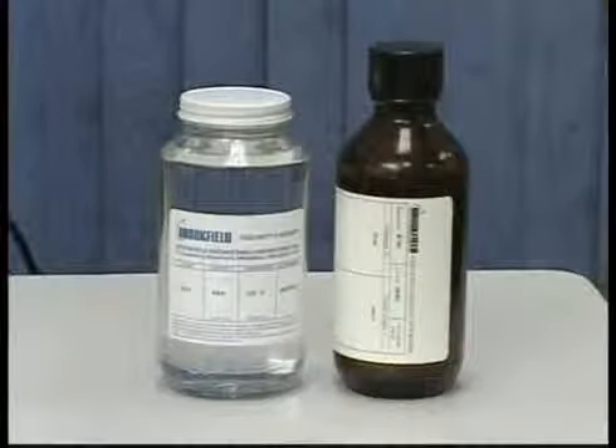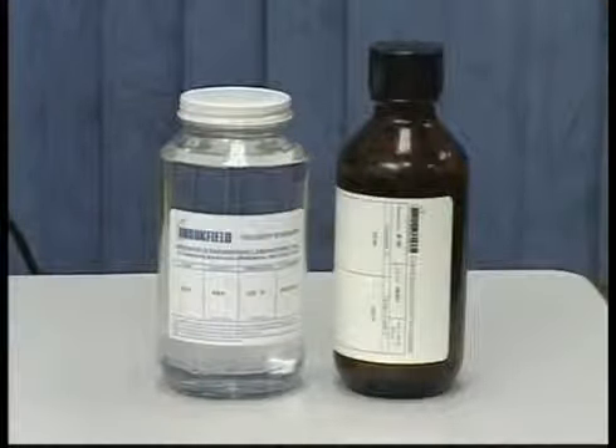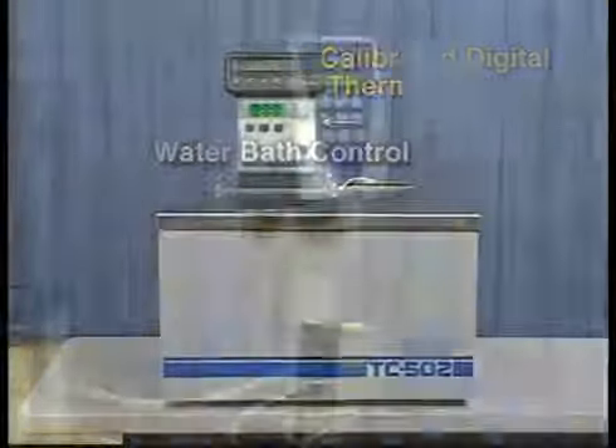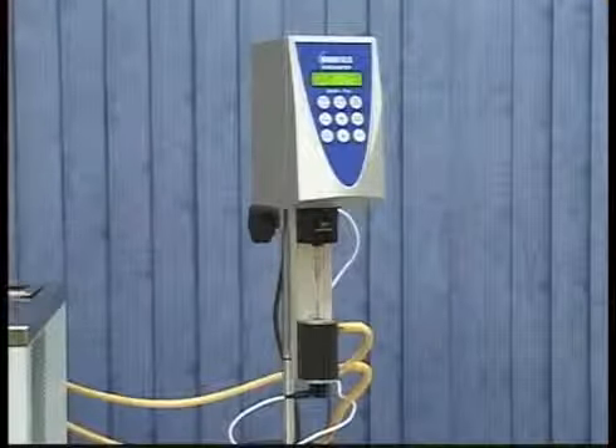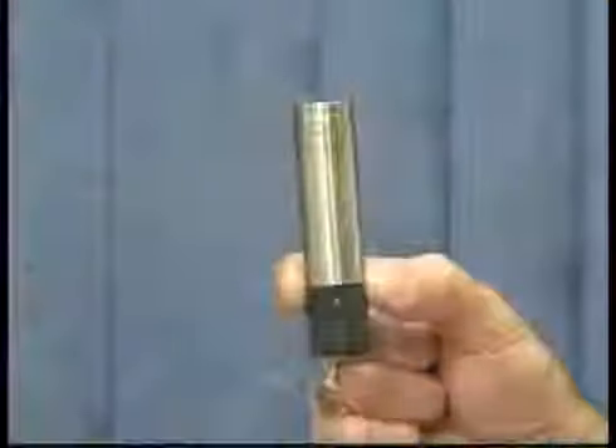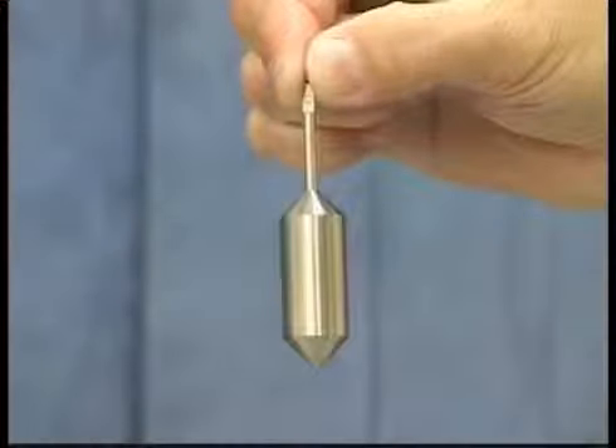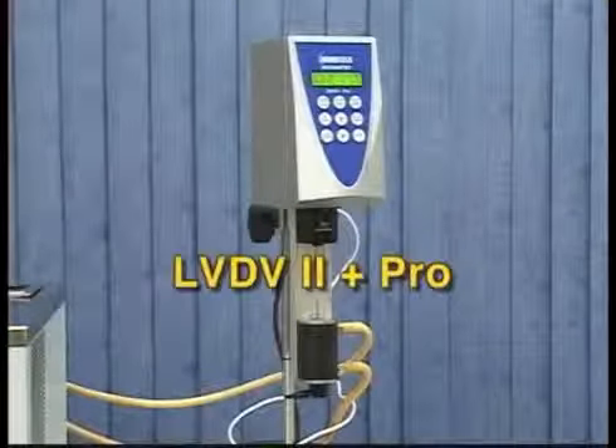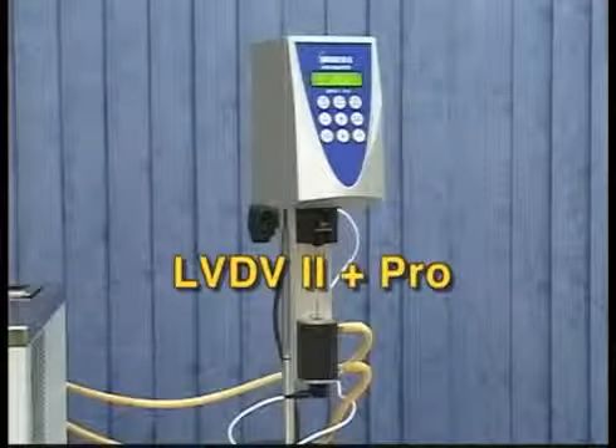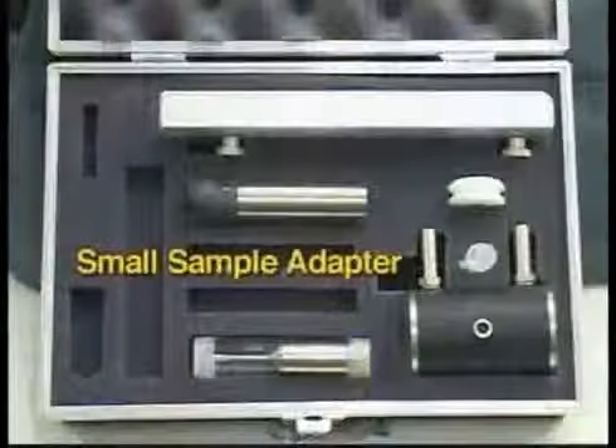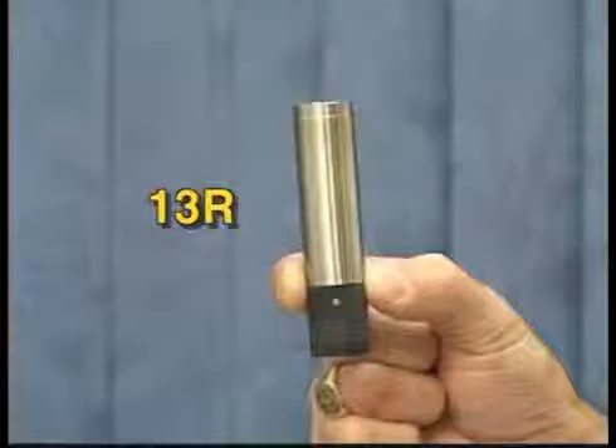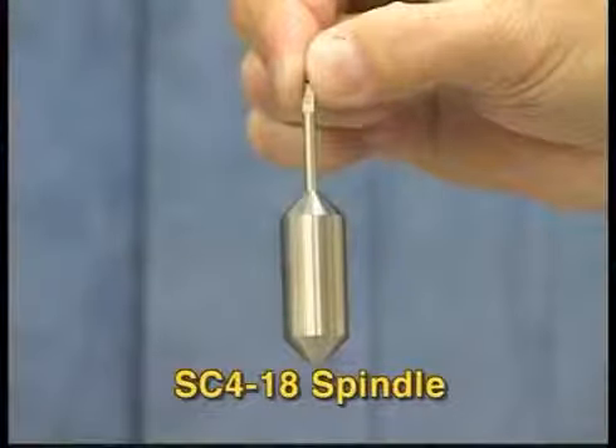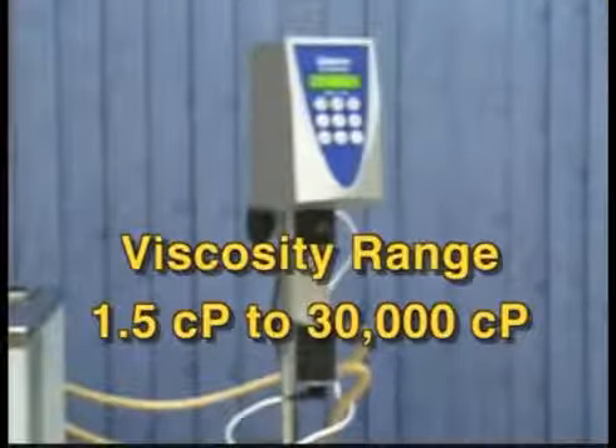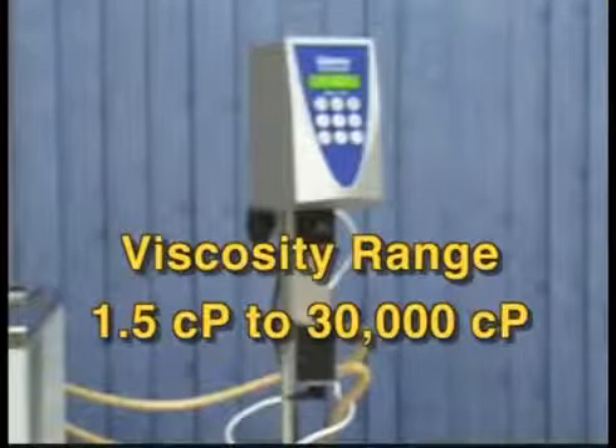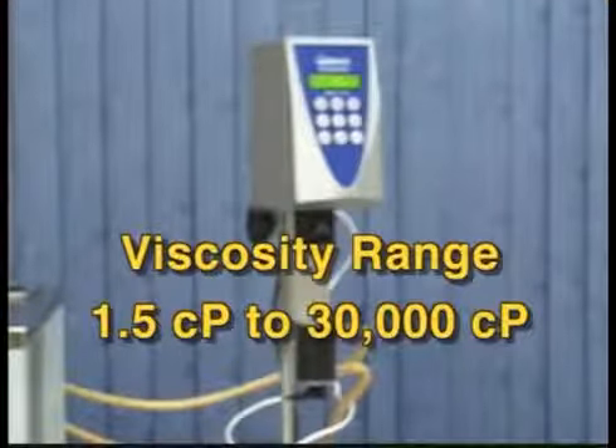To perform a calibration check with these adapters, you will need a silicone or mineral oil viscosity standard fluid and a water bath. Select a viscosity standard fluid based on the torque range and model of your instrument, the adapter chamber, the spindle, and the rotational speeds that you will be using. For example, an LV torque range DV2 Plus Pro viscometer using a small sample adapter with 13R chamber and SC4-18 spindle has a viscosity range of 1.5 centipoise to 30,000 centipoise, depending on the speeds being used.